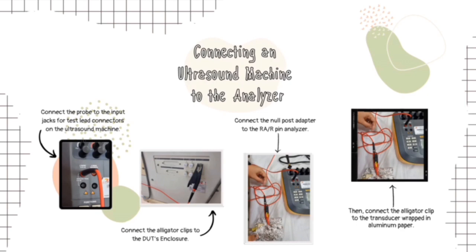At first, connect the probe to the input jacks for test lead connectors on the ultrasound machine, and then connect the alligator clips to the DUT's enclosure. Then, connect the null post adapter to the RA/R pin on the analyzer as shown in the figure. Then, connect the alligator clip to the transducer wrapped in aluminium paper.